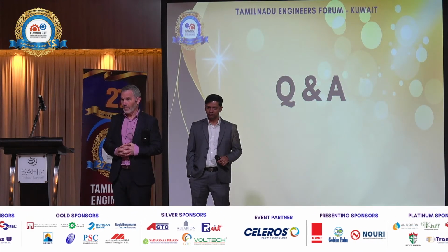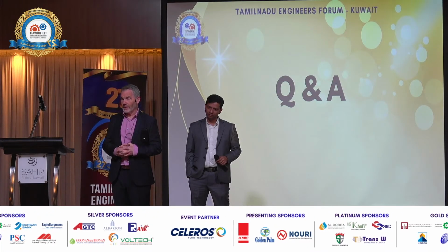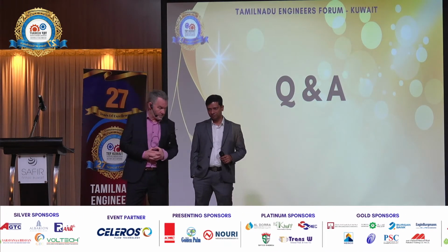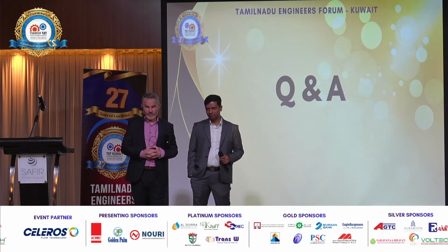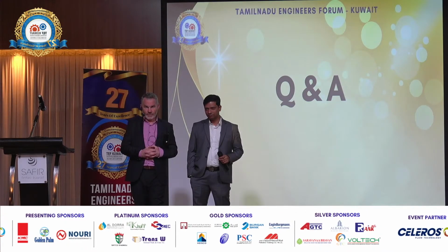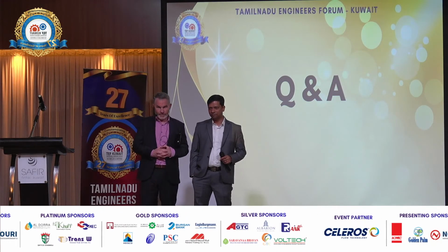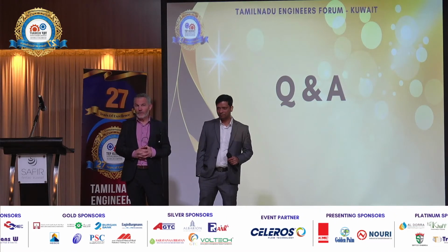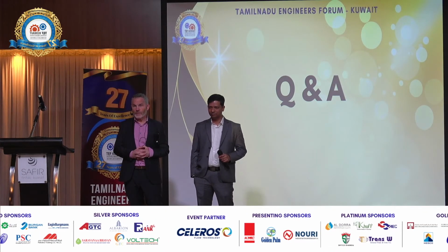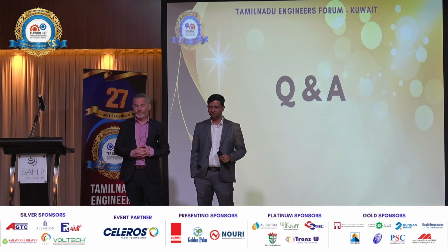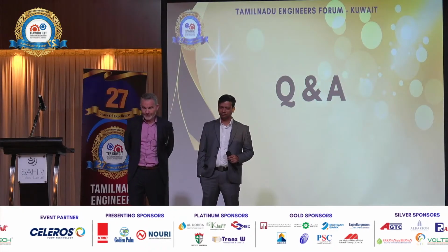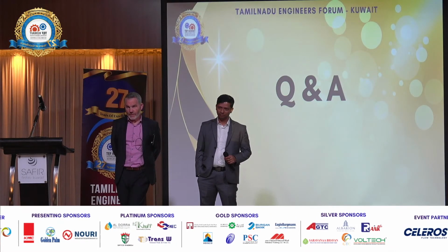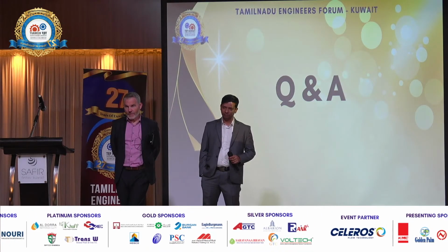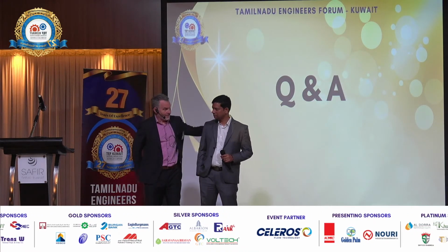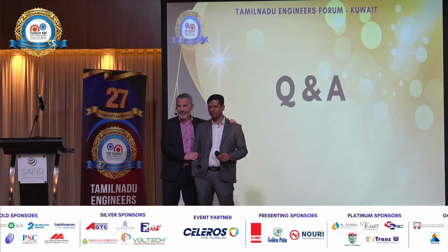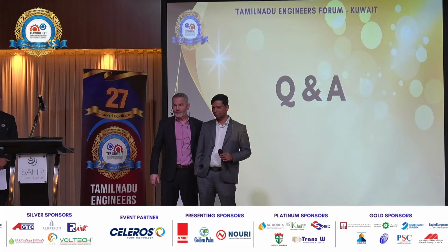Okay, thank you. The last question, actually, is about re-rating. Some of our main pumps are having issues due to the low flow requirements. They were over-designed, maybe due to conceptual reasons, for some percentage, but we are actually utilizing only 30 to 40% of that. In that case, is it possible to change the impeller or the internals and use the same pump, or do we need to procure lower-rated pumps?